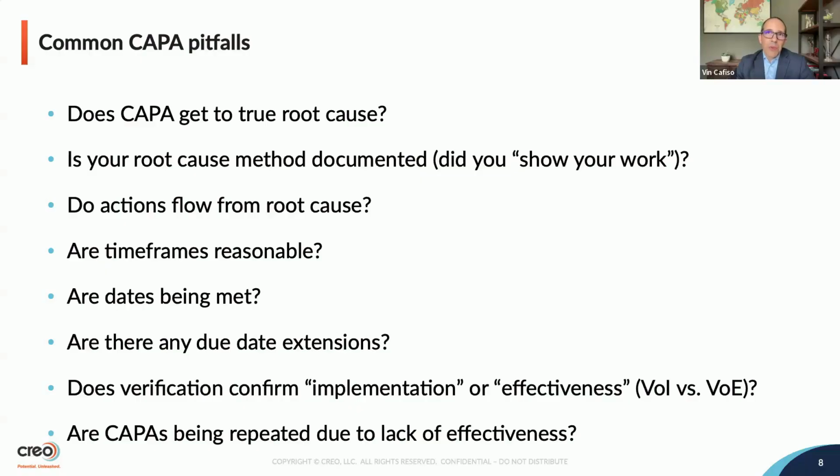And actually, during a future FDA inspection, the FDA investigator will ask to see your list of CAPAs since the last inspection, right? If you're lucky it's 3 years, but it may be a year later, depending on the severity of the 483. They're going to look at the CAPAs that have been generated as a result of not just the 483s, but of all of your quality issues. And they're going to be looking to see the similarities between the CAPAs identified as a result of the 483 and any other CAPAs, to see if the company is not effectively handling the CAPAs.